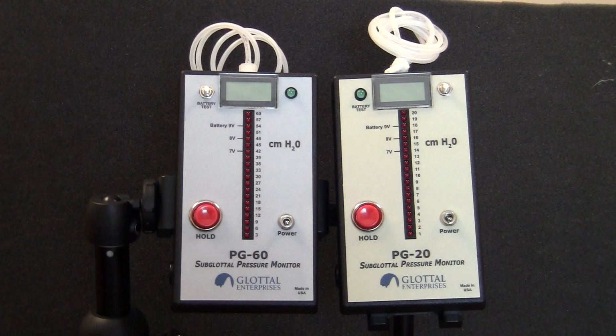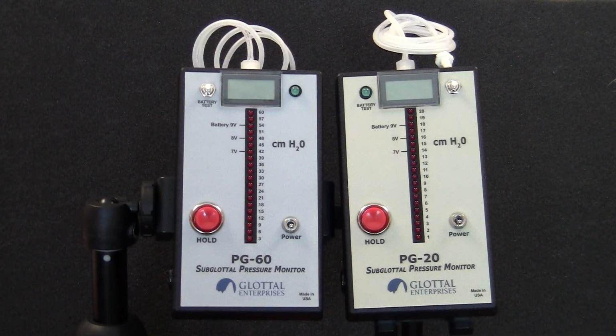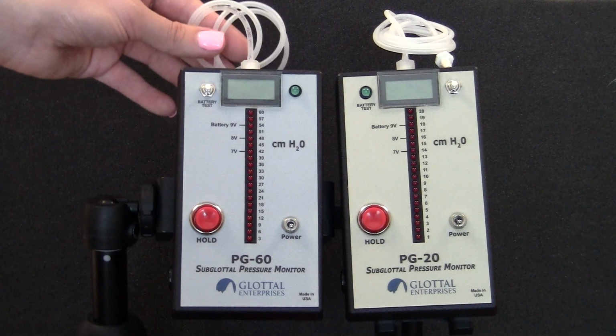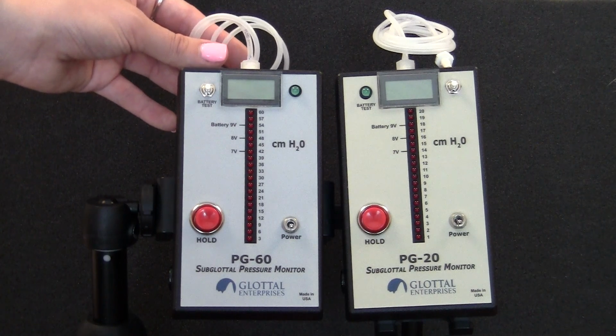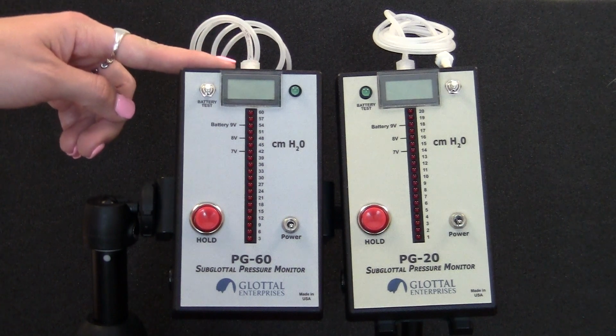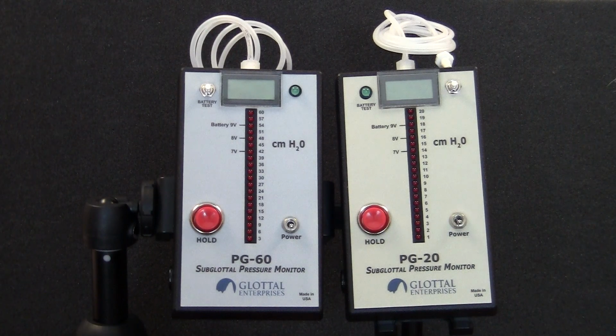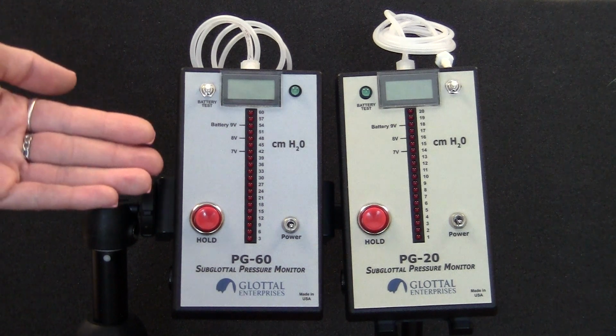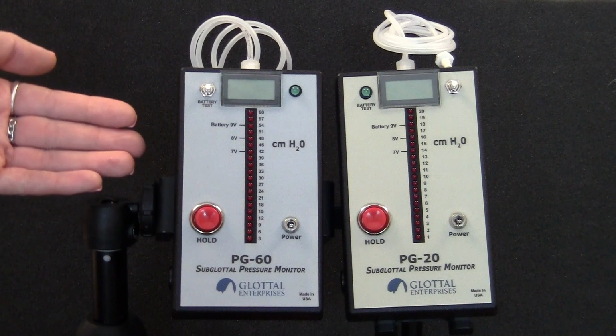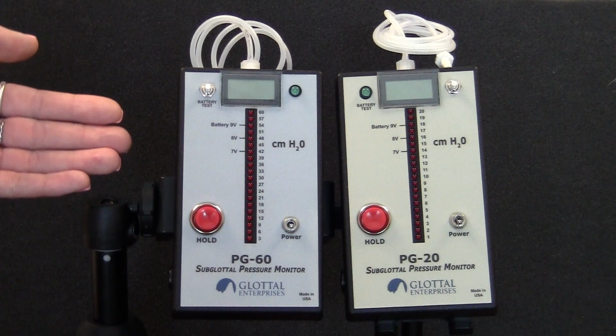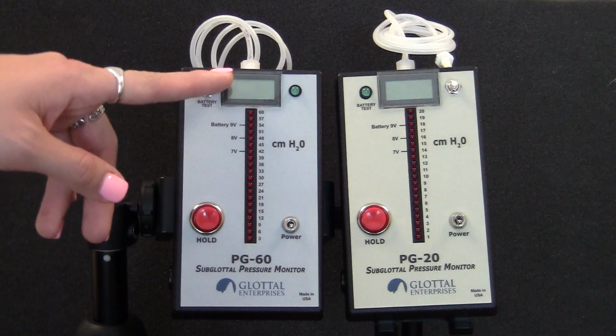The PG-60 measures up to 60 centimeters of water and is designed to be useful in monitoring very loud speech and singing. In the PG series, a pressure transducer measures the air pressure in the mouth, or intraoral pressure, during a P consonant by means of a tube that is placed between the subject's lips. This tube is connected to the PG-20 and PG-60 via a standard luer connector and can easily be removed to be cleaned or replaced when necessary. A patented electronic circuit derives and displays an estimate of the subglottal pressure from the intraoral pressure. This value of subglottal pressure is displayed on both an LED linear display and on a digital panel meter.